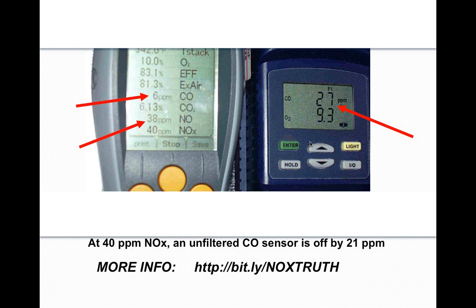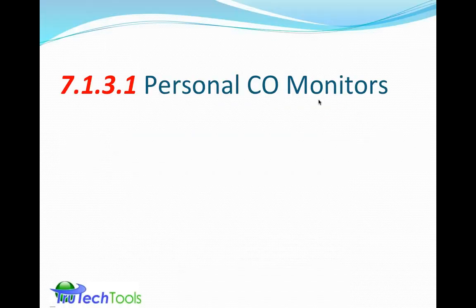We're also seeing this instrument on the left has the ability to measure the nitric oxide value, so it's reading about 38 parts per million, 38 to 40. The way NOx affects the CO sensor, it's also an acid gas, it affects it at a ratio of about 50%. So 50% of the 40 ppm or so is about 20, and that leads to this being off by about 20 parts per million. So the combination of nitric oxide plus the CO is being shown here as only CO on this meter. Now, if you applied a NOx filter to it, you would see that drop down to the 6 or 7 range and give you the correct reading. And because CO is the basic input to the CO-AirFree calculation, you must get that correct. If you don't get that correct, you're going to have an inflated CO-AirFree number and then trouble with that.